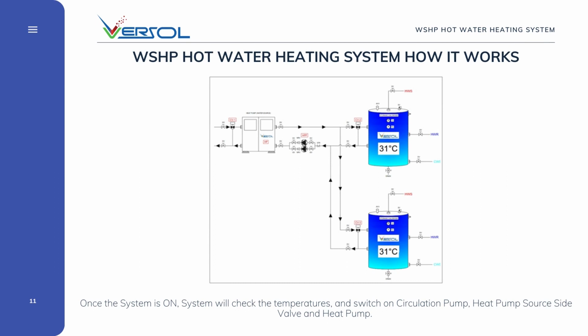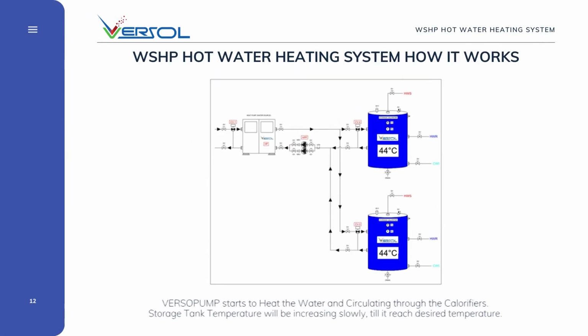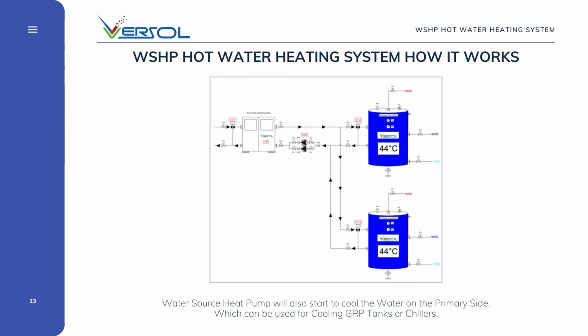Once the system is on, the control system will check the temperatures in the tank, and switch on the circulation pump, the heat pump source side valve and the heat pump. VersoPump starts to heat the water in the circuit, circulating through the calorifiers. Storage tank temperature will increase slowly till it reaches the desired temperature. The water source heat pump will also start to cool the water on the primary side, which can be used for cooling GRP tanks or chillers.